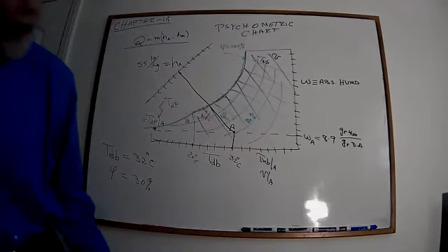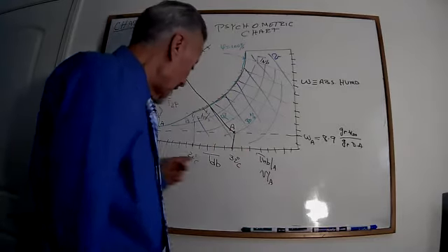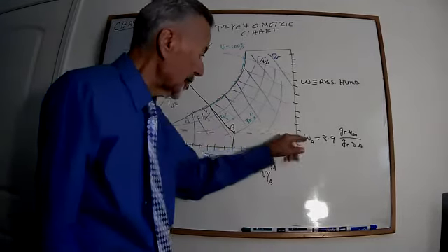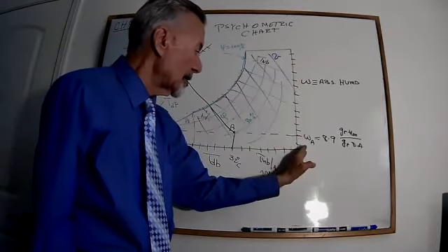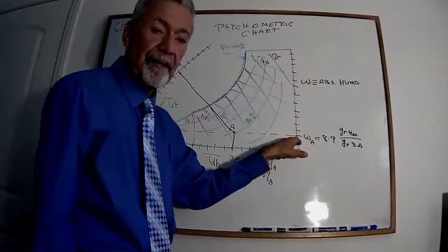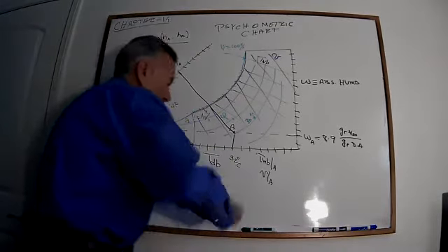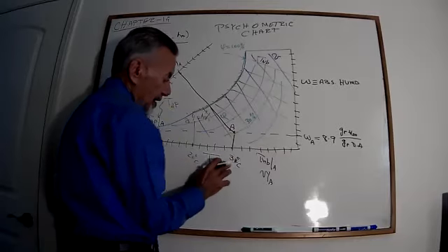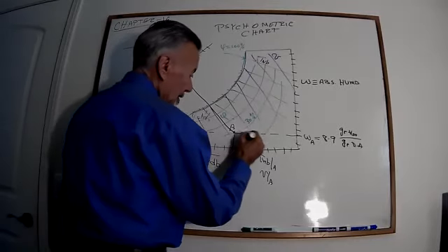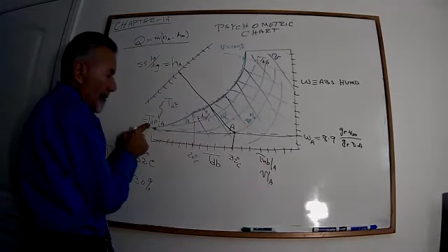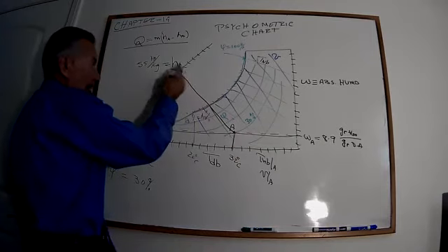How did we get the omega at the beginning, the 8.9? Once you find the point A, you go parallel to the dry bulb axis until you hit the axis of omega. That's how you find omega. What I did, I found point A based on the 30% and 32 degrees. Then I go to the right and find omega. If I go to the left, I find dew point. I take a perpendicular line, I find the enthalpy.